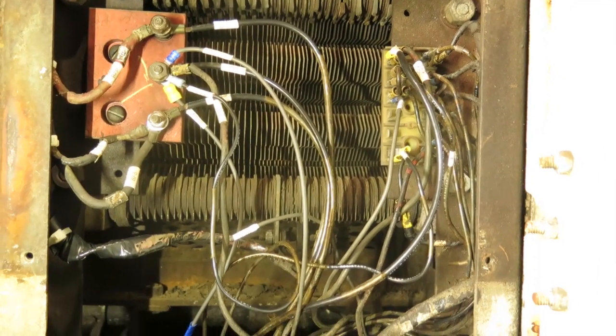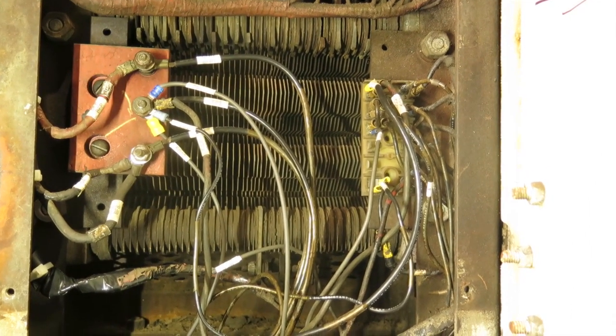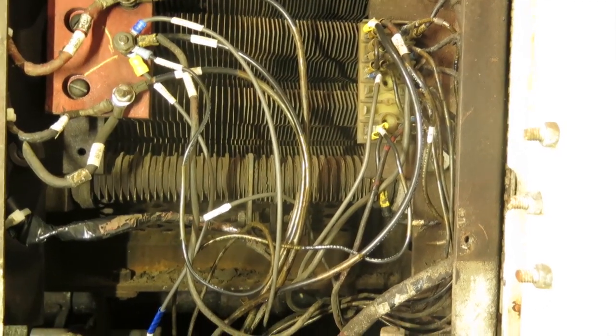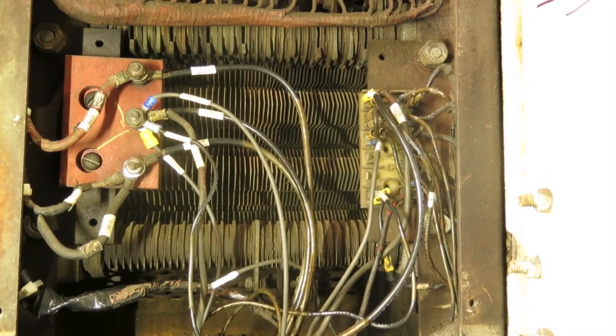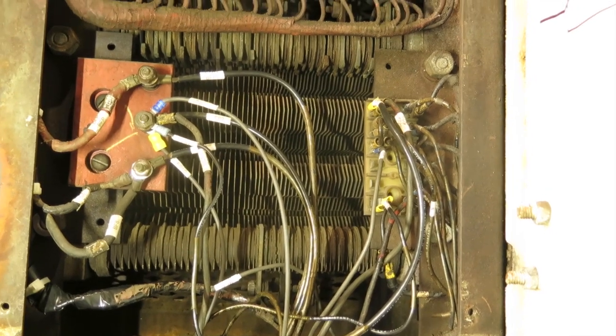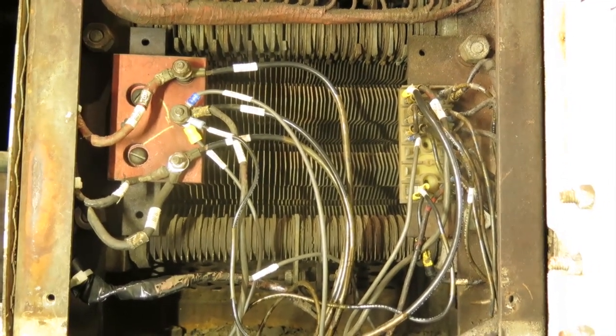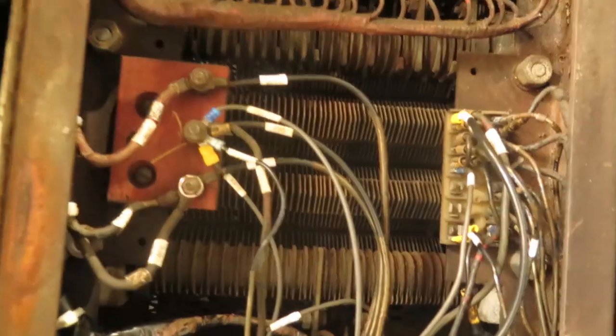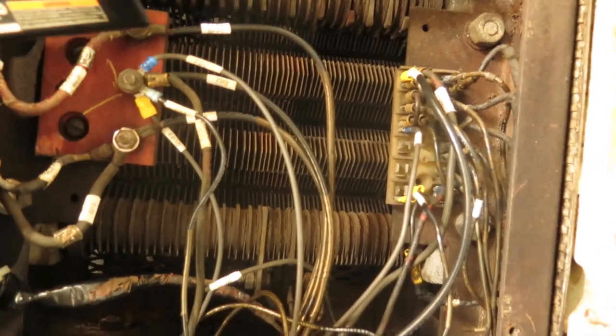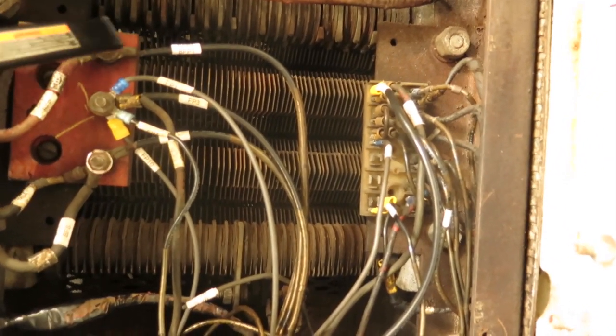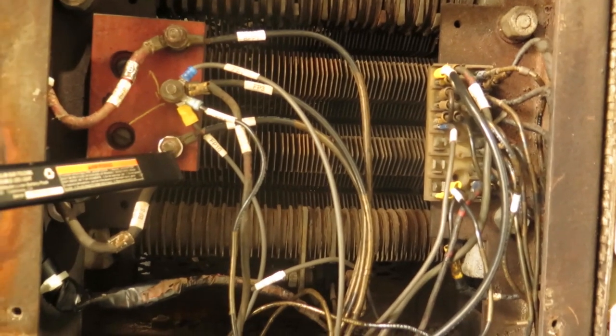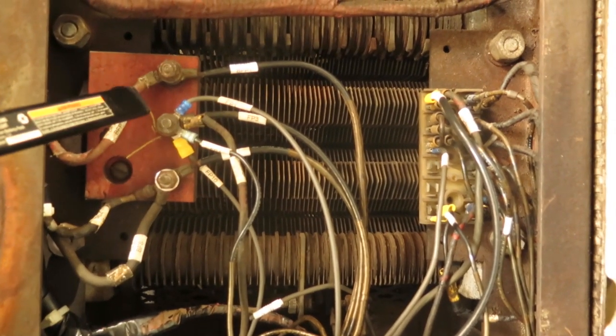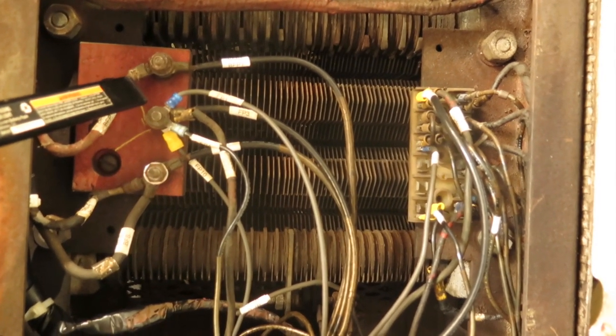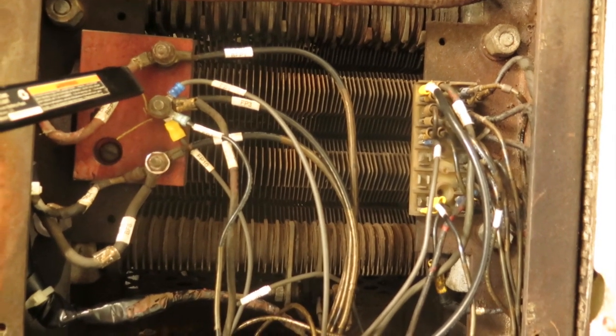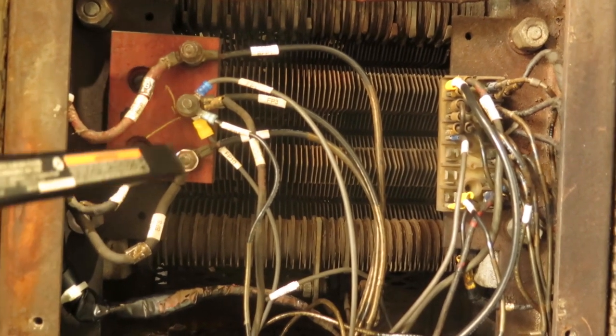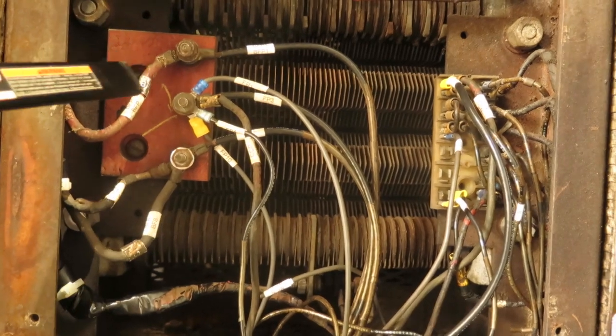This is the terminal board at the bottom of the load regulator. A lot of those have nothing to do with the load regulator itself, it's just where the power or wiring comes in from the electrical cabinet. However, the two wires here and here are the positive to the load regulator, which is fused. It comes from the battery field contactor, and the negative is here.